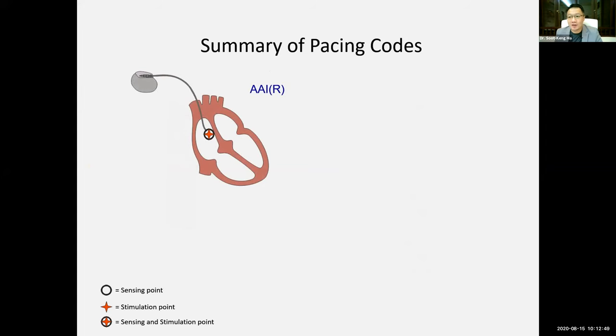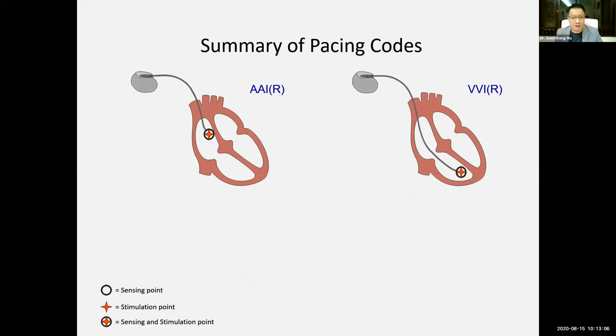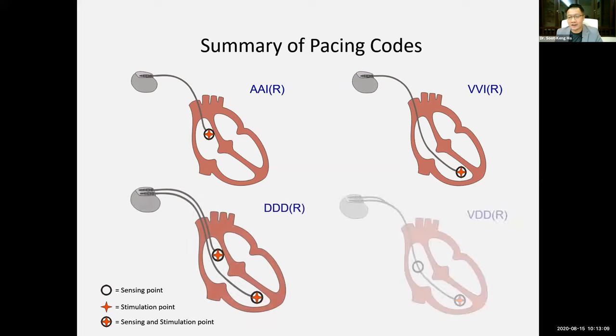Hence, in summary, we have a lot of other pacing codes. You can use the same concept to decode all these different iterations of codes. AAI means pace in the atrium, sense in the atrium, and if you sense intrinsic activity, you inhibit yourself. VVI, as I spoke about earlier, DDD, I spoke about earlier, and VDD. Now VDD is actually a single lead, dual chamber system, whereby it can sense both the atrium and the ventricle, but only paces the ventricle. This is a very special form of pacemaker.